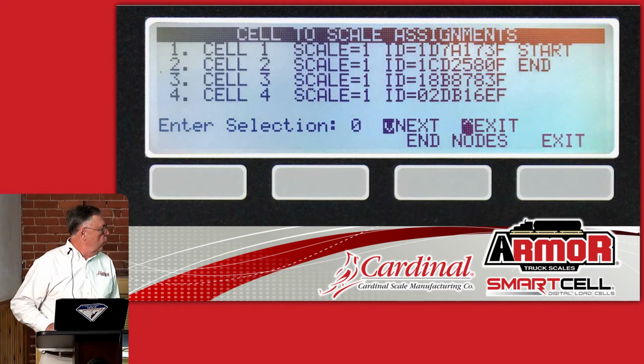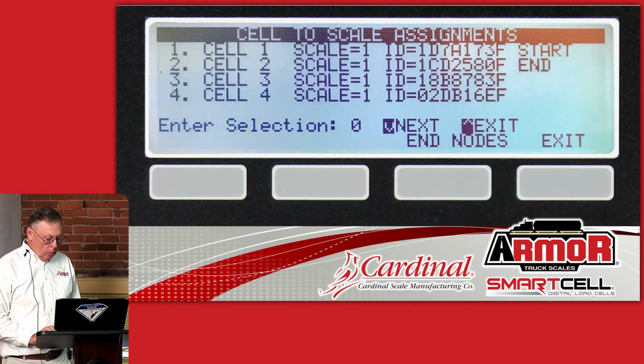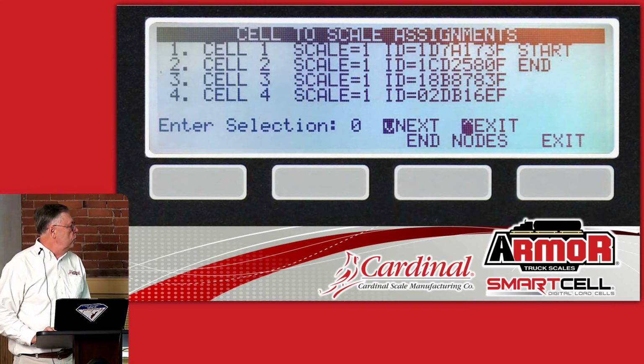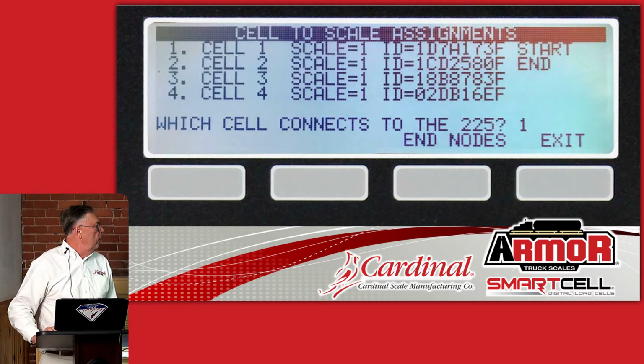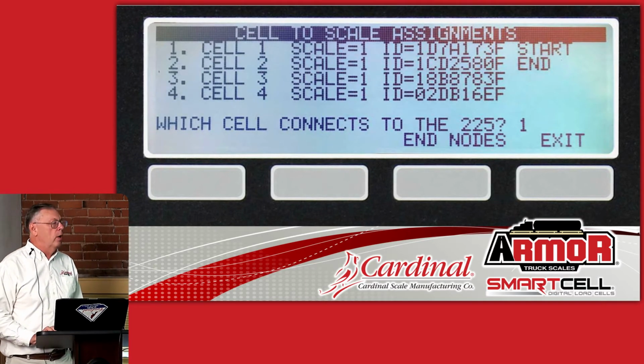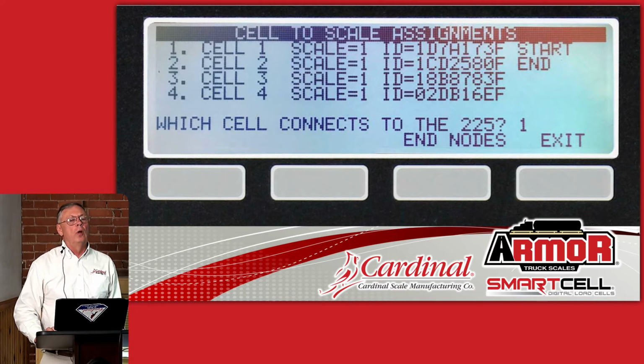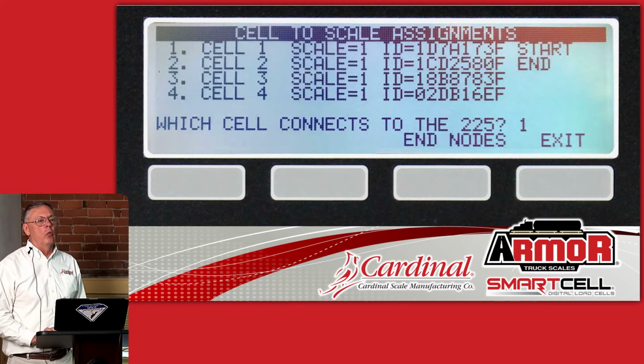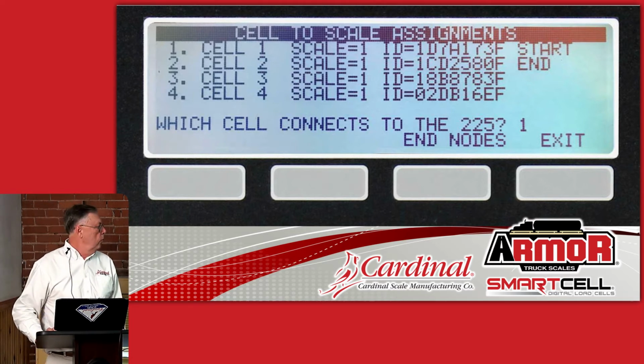But the button, the third soft key to the right that says end nodes, what he's going to have to do is push the end nodes button, and the indicator is going to ask him which load cell connects to the 225. We don't care which one it is, just tell us which load cell you hook the indicator to. In this case, it's load cell number 1.